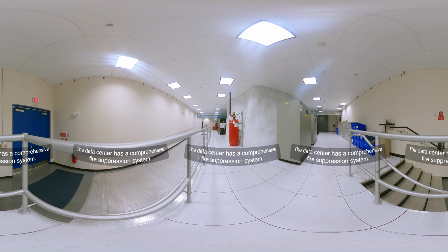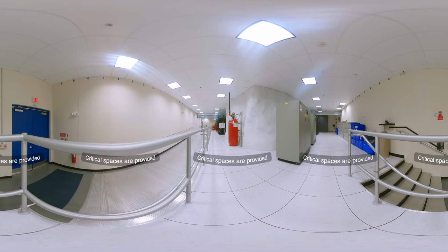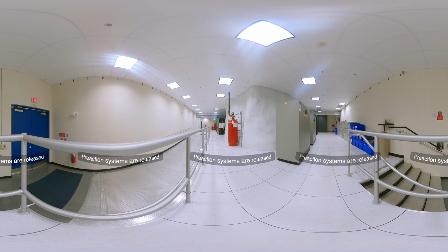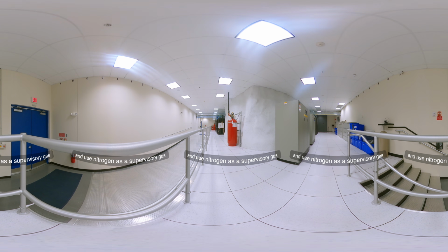The data center has a comprehensive fire suppression system. Critical spaces are provided with double interlock pre-action systems, which are released by electric and pneumatic means and use nitrogen as a supervisory gas to help prohibit corrosion.